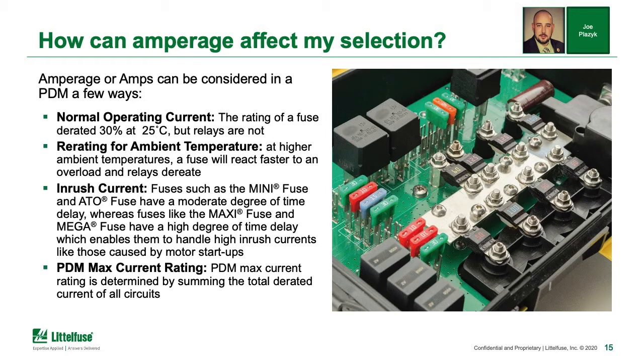Along with higher ambient temperatures, we need to consider the inrush current. Inrush is the sudden rush of current, which is most commonly seen during startups. And we have our max PDM current rating. Max PDM rating is determined by summing all of the total derated current of all your circuits. When you have these together, these are the amperage considerations when selecting or designing a PDM. And on here, Jeff will tell you how we distribute power.